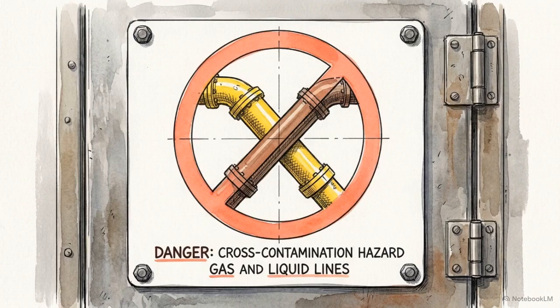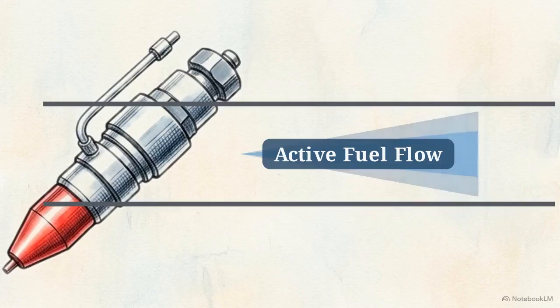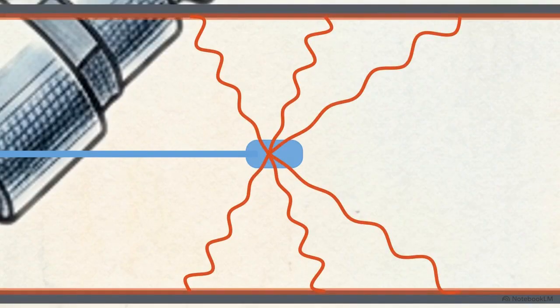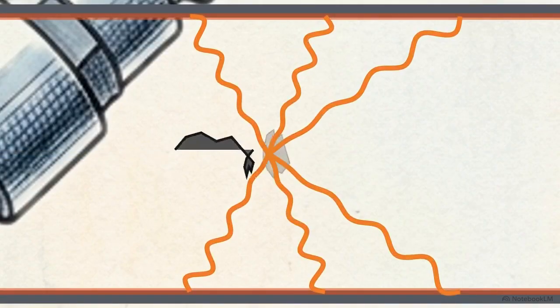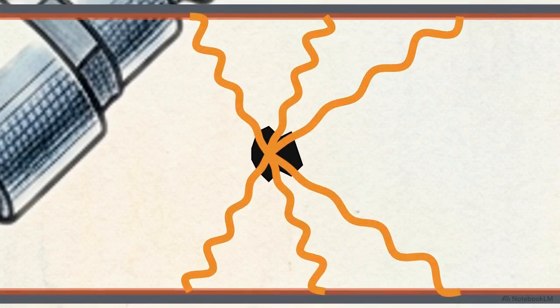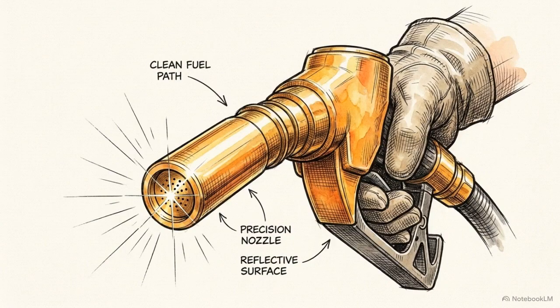Operating procedures strictly prohibit mixing natural gas and liquid fuels during a single run. When running on liquid fuel, on shutdown, the manifold must be completely drained to avoid coking. If diesel remains in the hot nozzles, the residual engine heat bakes the fuel into hard carbon deposits that permanently clog the spray orifices. Precision timing during the start sequence and absolute drainage on shutdown are the primary defenses against fuel system failure or permanent nozzle damage.